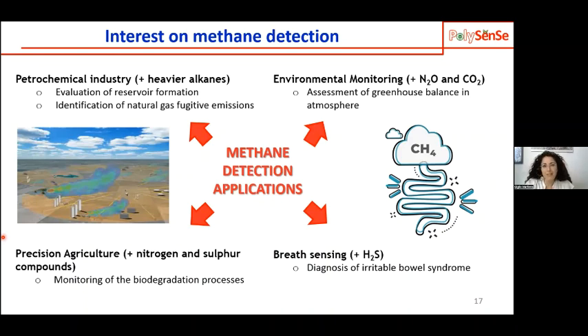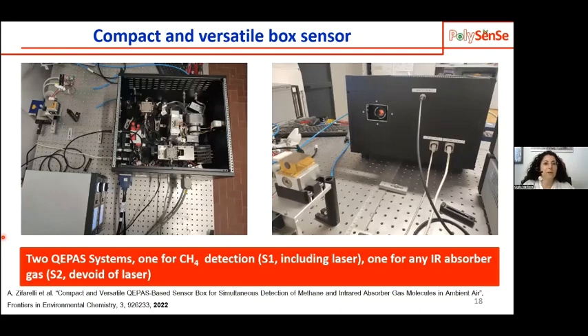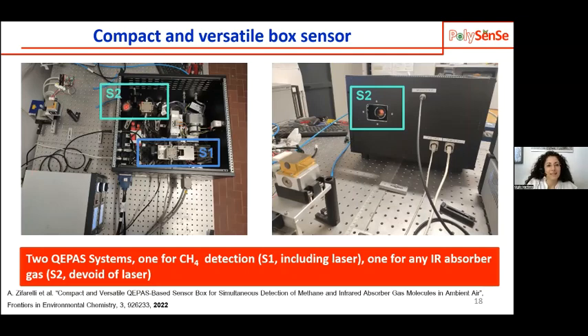That's why we developed our custom, compact, and versatile box sensor that is composed of 2 QEPAS systems. The first one, indicated with S1, consists of the QCL here, so a laser source, a focusing lens, and the acoustic detection module. The second one is devoid of the laser source. The laser source is set externally. So it just consists of the focusing lens, which is here, and the acoustic detection module.